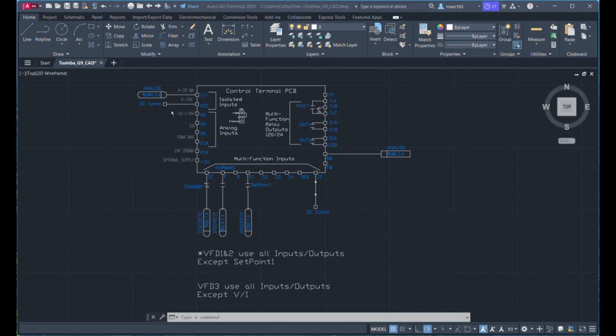To simulate the 3 chemical tank pumps, I used 3 Toshiba VFDs. To wire the VFDs to the Modicon M340 PLC, wire VI, which is also your speed reference, to your analog output card with ICC as your DC com. Next, wire AM, which is your feedback, to your analog input card with CC as your DC com.